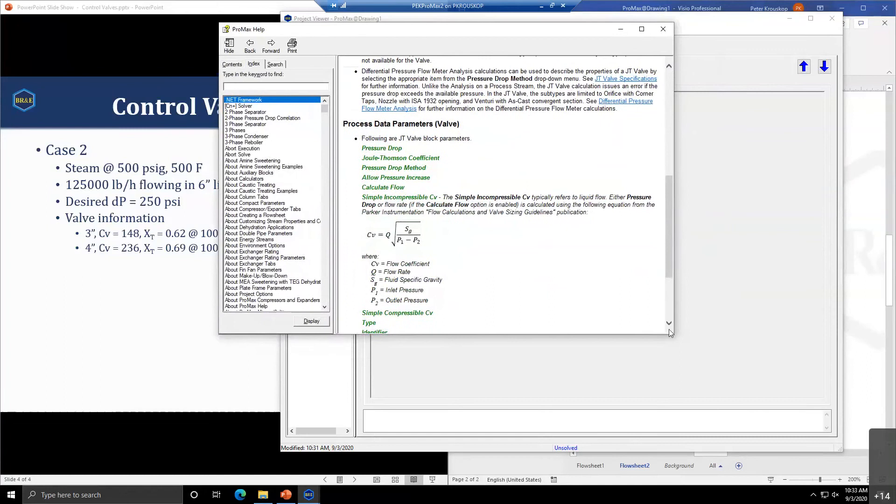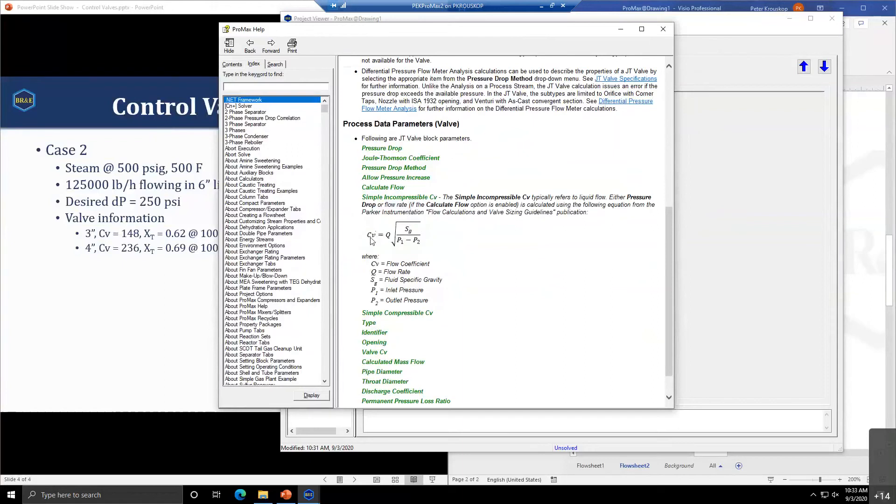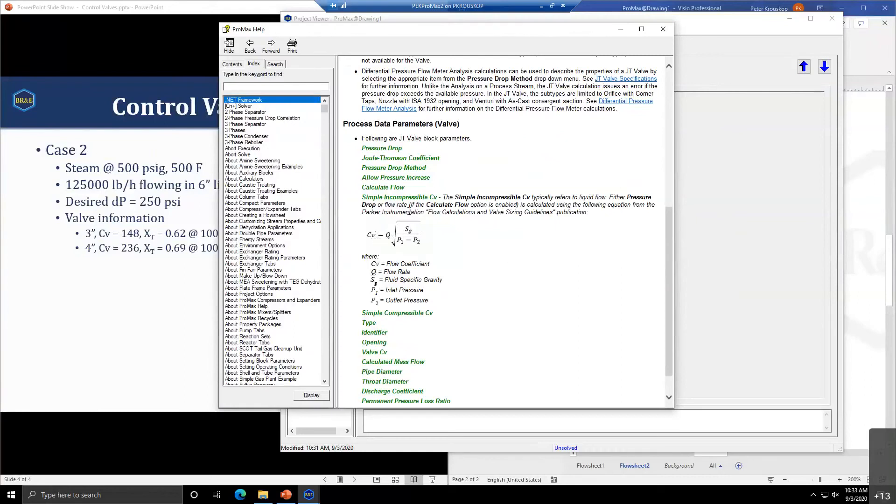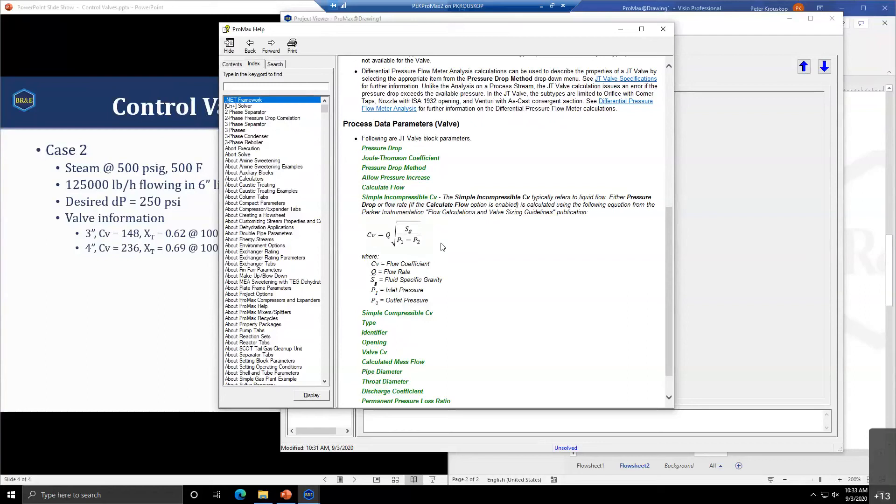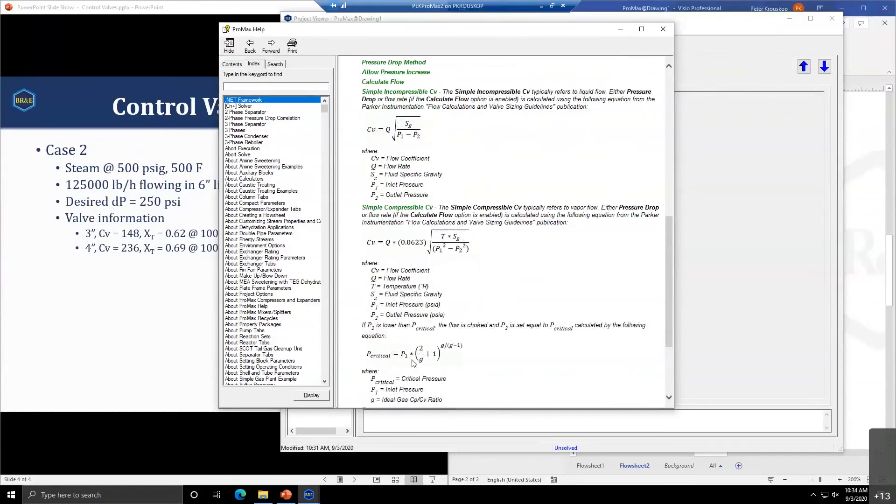The simple incompressible CV equation never chokes, so it will not calculate a choke condition for liquids. But it is dependent on the specific gravity of the liquid, the CV you put in, and the flow rate going through the system. In a very simple sense, it's going to give you what your pressure drop would be given a flow rate, a particular composition, and the CV of the valve. This is a very basic equation, so obviously it's not going to account for every aspect of the valve.